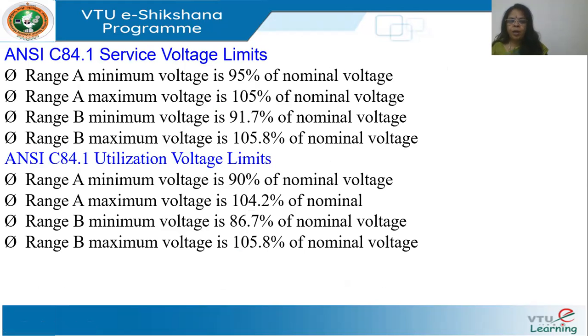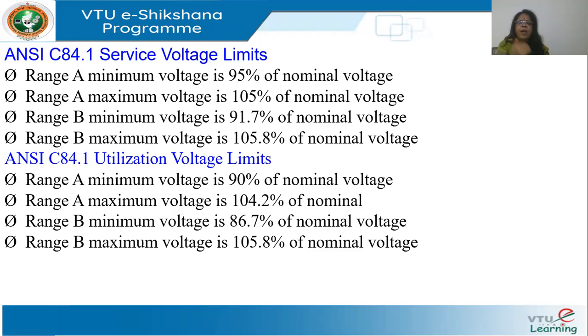For ANSI C84.1 service voltage limits: range A has a minimum of 95% and maximum of 105%, that is plus or minus 5%. For range B, the range is between 91.7% to 105.8%, meaning a larger deviation is acceptable, though not optimal. This applies at the customer's premises.